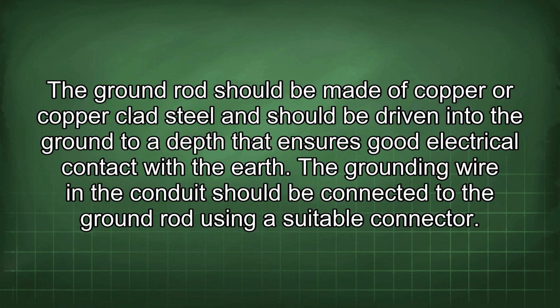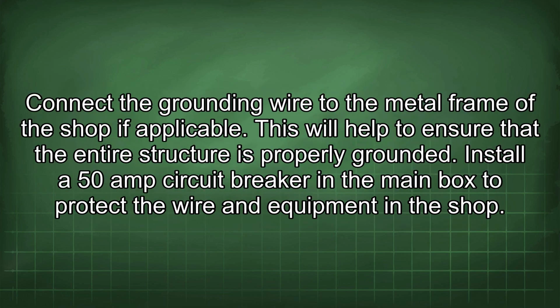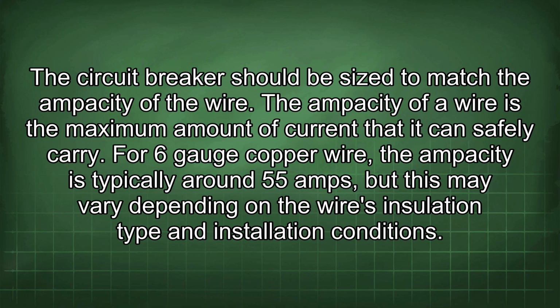The grounding wire in the conduit should be connected to the ground rod using a suitable connector. Connect the grounding wire to the metal frame of the shop if applicable. This will help to ensure that the entire structure is properly grounded. Install a 50-amp circuit breaker in the main box to protect the wire and equipment in the shop. The circuit breaker should be sized to match the ampacity of the wire.